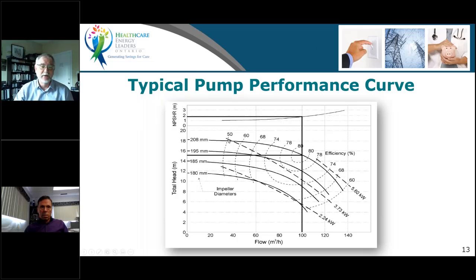And if we go even further, not only do we drop efficiency, but we're probably going to destroy that pump. I'll show you what can happen in a few minutes. Likewise, if we push the pump higher, that is, if we use more speed to get more flow, or we reduce the head on the system, the pump will try to operate up here, because if we reduce the head on the system, we're going to move up there as well. That's going to cause trouble as well.